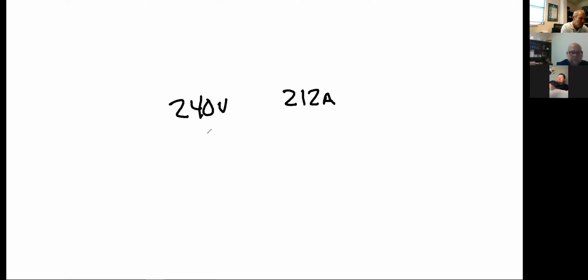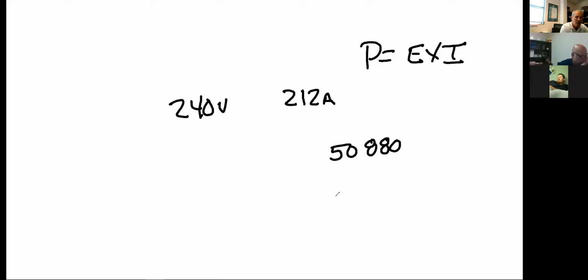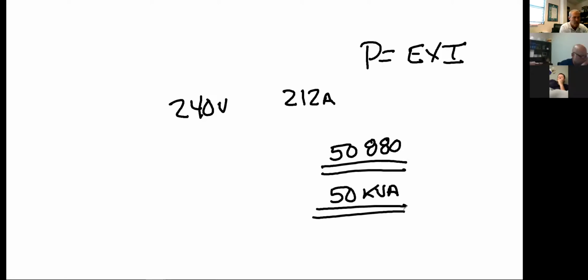I don't have two different voltages. But I am looking for P. kVA is power. So what's the math? P equals E times I. 240 times 212. Yes, 240 times 212, which is? 50,880. All right, well, that's going to be close to one that we're familiar with. And what is that? I'm looking for the kVA transformer. 50 kVA transformer, right? That 880 is nothing. 50 kVA is what I need.